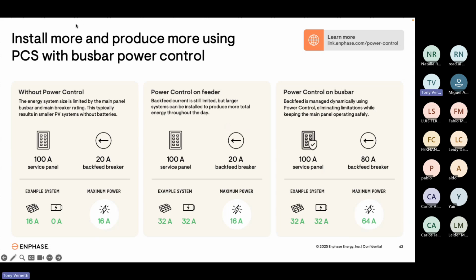Here we have a couple of examples. On the far left, we have what you're typically limited to on a 100 amp service panel, according to the United States National Electrical Code. I don't know exactly what electrical code is followed in the Bahamas or Cayman Islands, but this probably is still going to be useful. In the US, you'd be limited to a 20 amp backfeed breaker on a 100 amp panel, which is a very small solar system, and there's really no capacity available for a battery.